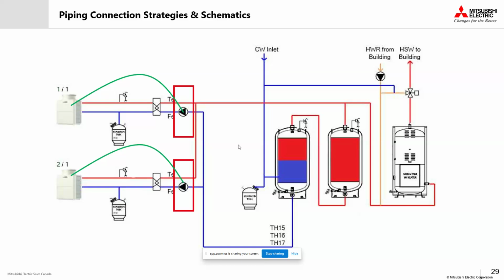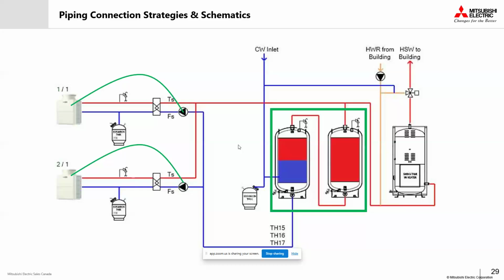So on the secondary or load side, we see some variable speed pumps that are used to match the primary flow and delta T. This is critical for maintaining that system efficiency and proper heat transfer across that heat exchanger. And next is where you might notice a slight deviation from a traditional domestic hot water loop. As you see, our hot water storage tanks are installed in series to promote stratification throughout the tanks. I'll get into more of how this all works in a couple of slides now.